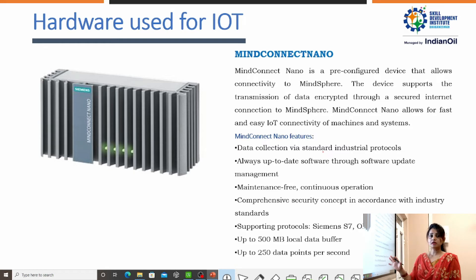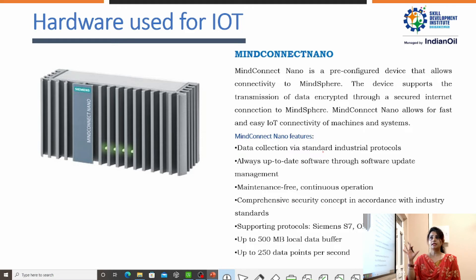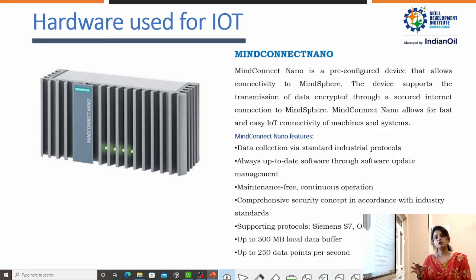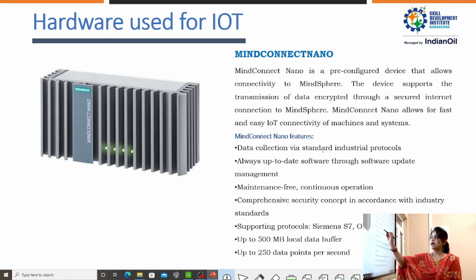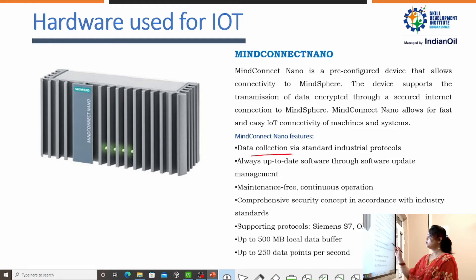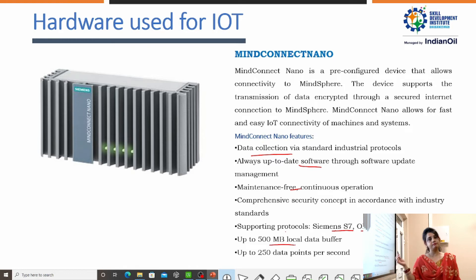Next is MindConnect Nano. This is the hardware required for IoT devices. It is a pre-configured device that maintains connectivity to MindSphere only, and it is required for maintaining fast and easy IoT connectivity. It also plays the main role in the transmission of data to MindSphere. Nano is mostly connected to all the controllers which collect all the data; this data is saved inside the Nano and then transferred to MindSphere. Its features include: it is a completely data collection device, it maintains up-to-date software, it is completely maintenance-free, it provides security, it supports the protocols Step 7 and OPC UA, and it provides up to 500 megabyte local data buffer.